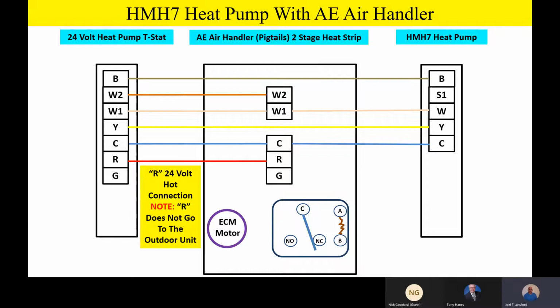But please remember, the R terminal does not go outside on this product, because the outdoor unit has its own power and all that kind of stuff, and it's just receiving signals from the indoor unit and thermostat. It does not require the R terminal to go outside.